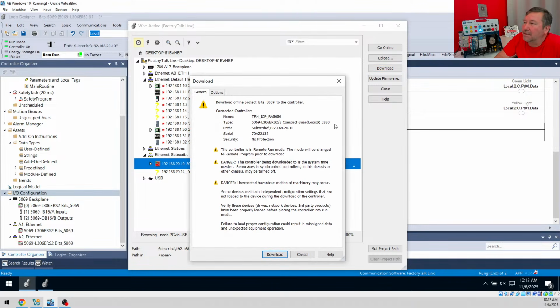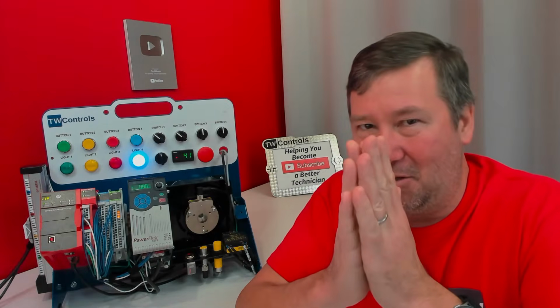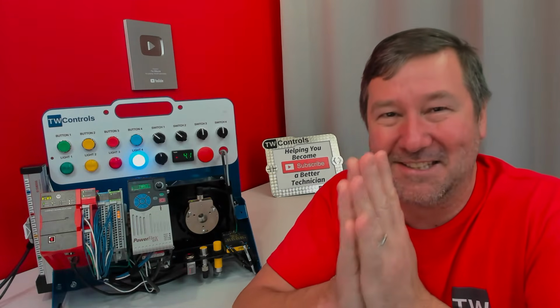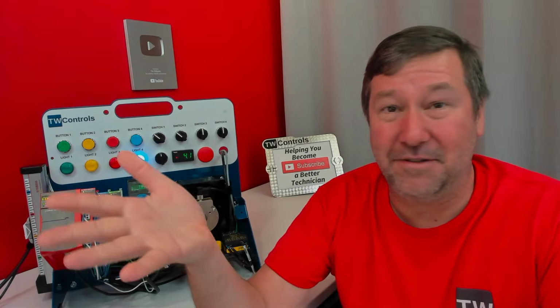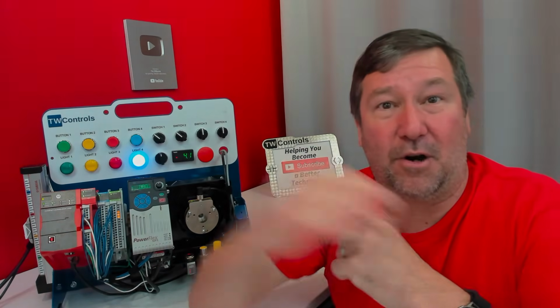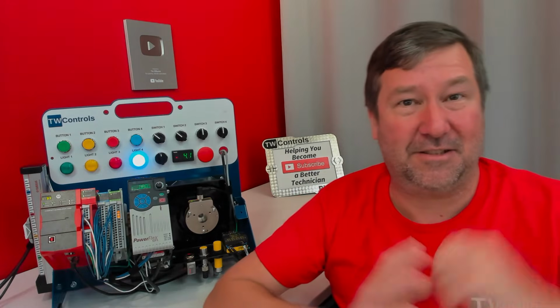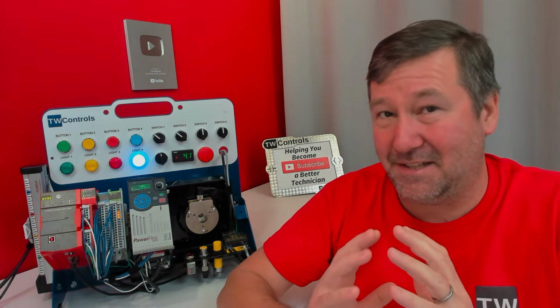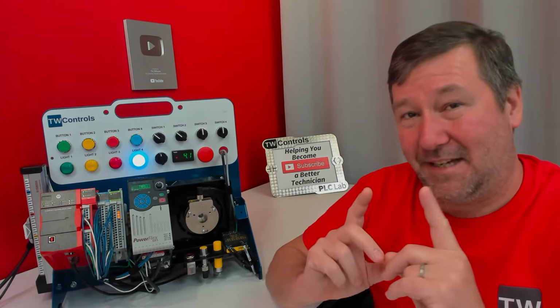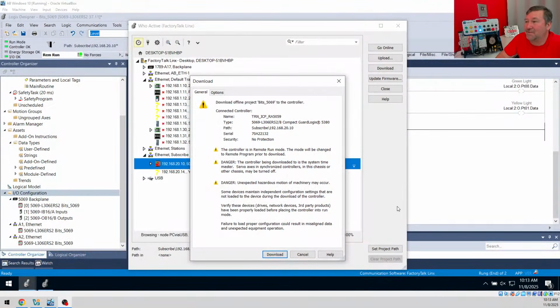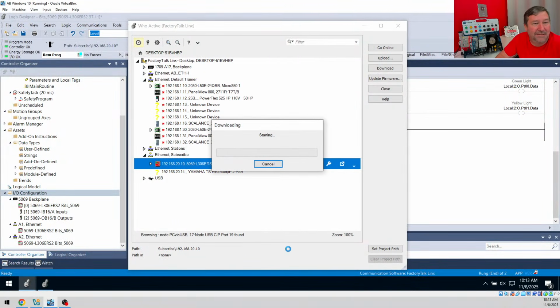And very important, there have been too many lawyers involved in this whole thing right here. I want you to read this top line. Download offline project to the controller. To the controller may be the most important three words in this whole warning box, because you're so used to being on the internet. You're going to download a program, you're going to download Studio 5000, you're pulling things into your PC, but PLCs are the opposite. That's your last chance to realize it. To the controller tells us the direction we're going to go. So once you're sure that's what you want to do, then we're going to hit the download button.